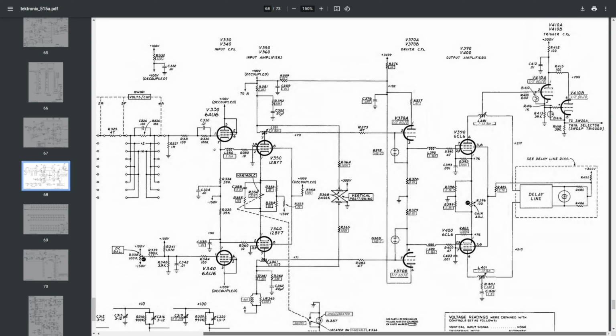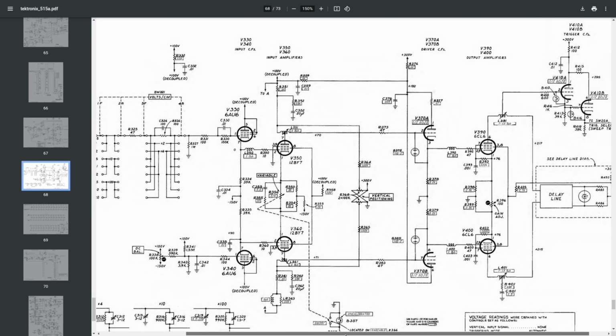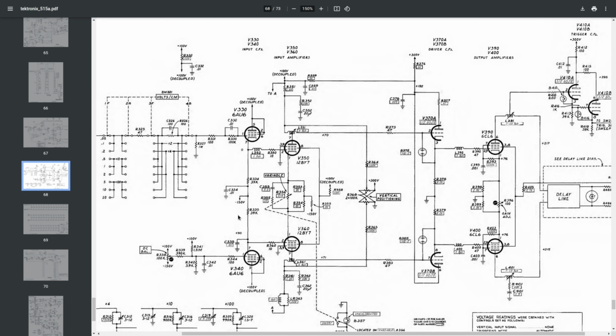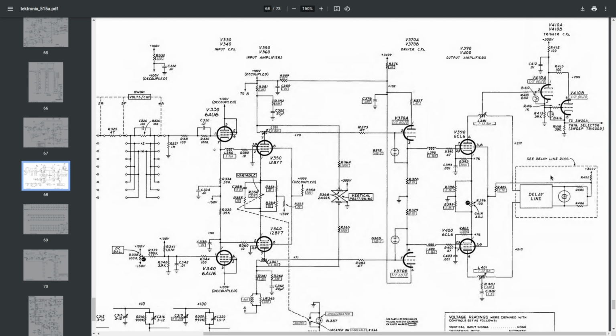By looking at it, you will notice that this one is pretty symmetrical, which indicates that this is a differential amplifier. And it makes sense because the deflection plates that go to the CRT, that are part of the CRT, actually need to be driven differentially. So as one voltage goes up, the other one needs to go down. That's why we have a differential amplifier here. However, there are multiple reasons for doing that, and I think this also helps minimizing stray capacitances, stray inductances, and so on, and it would be better for driving this delay line that we have here before the CRT.